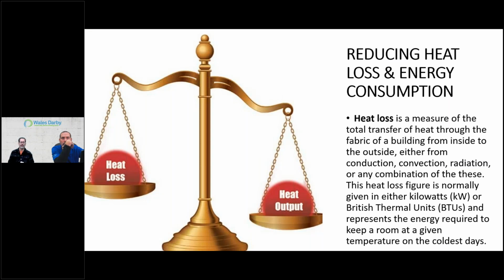And then all of a sudden I realize I'm still carrying the load of the house. So therefore I'm not going anything higher than 140, 150 maybe. I don't have to go to 180 anymore. The short cycling reduces. Comfort level is better. My efficiencies go up a little bit. Certainly my fuel energy dollars are working in my benefit.